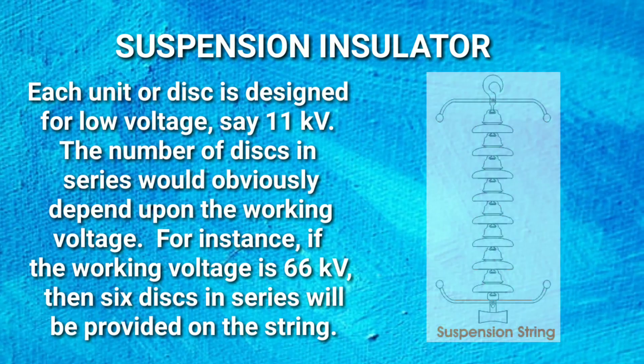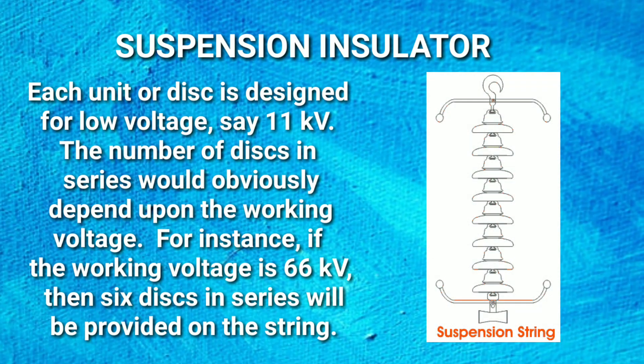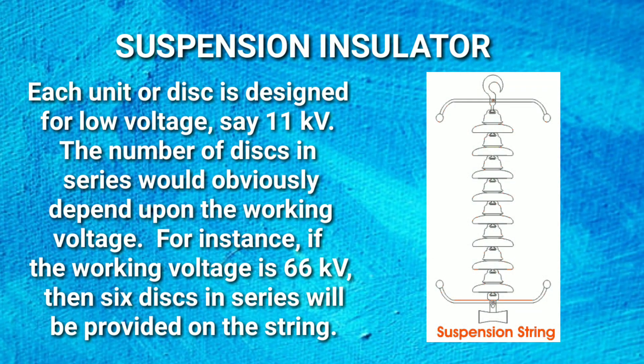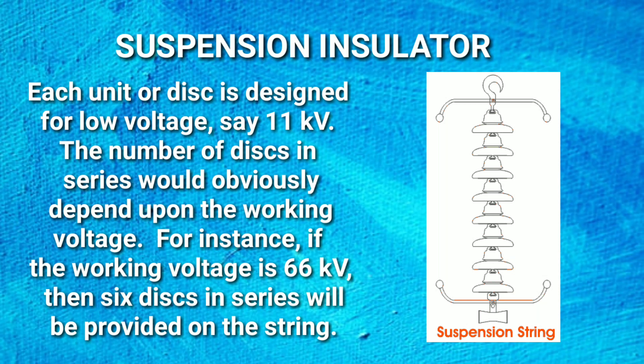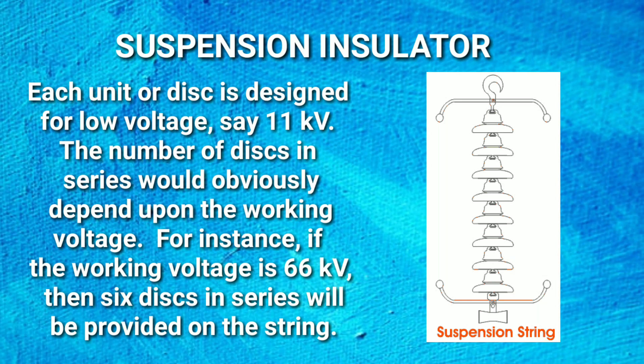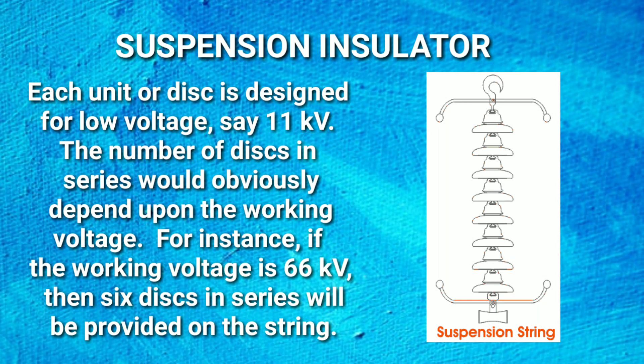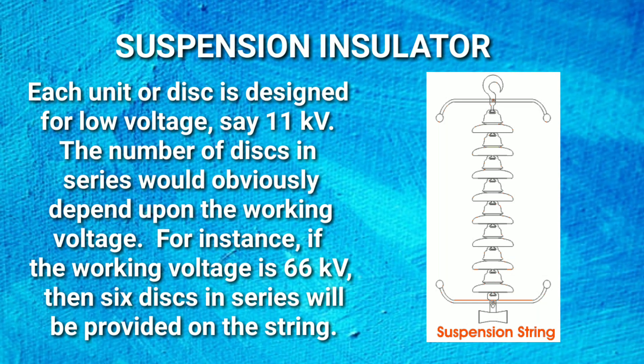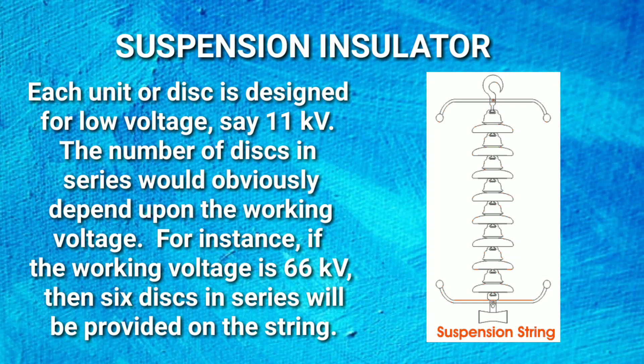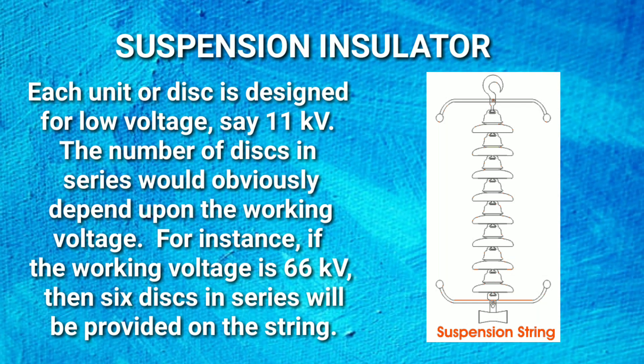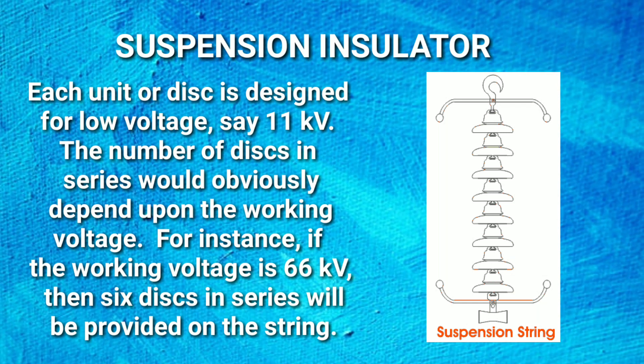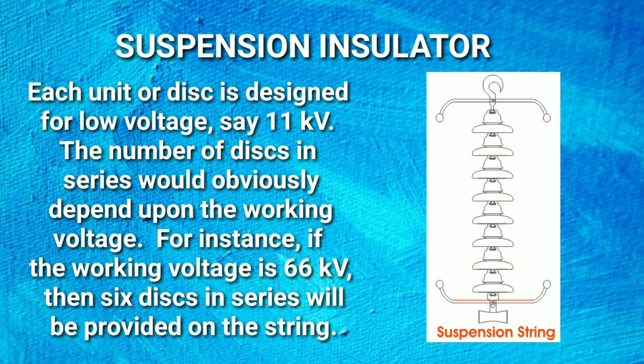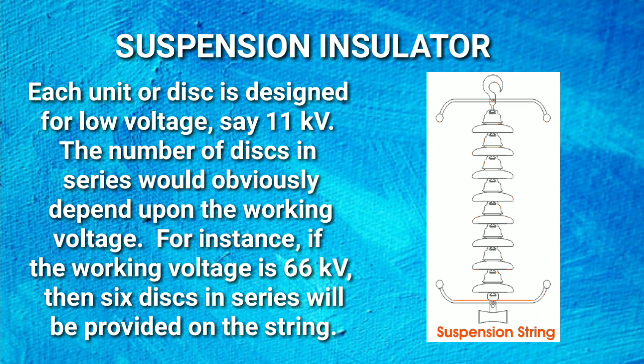Each unit or disc is designed for low voltage, say 11 kilovolts. The number of discs in series would obviously depend upon the working voltage. For instance, if the working voltage is 66 kilovolts, then 6 discs in series will be provided on the string.